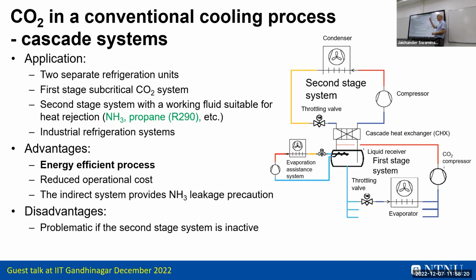No, I would rather send the CO2 in the pipes and suck it back, with evaporators in the different air handling units where you need cooling. You could have one or two centralized CO2 systems connecting all these evaporators, and where you need heat, you put the heat pump to collect heat from all the buildings with a CO2 network, similar to this. That pipe would be much smaller compared to the chilled water pipe, and the pumping power would be zero, because the CO2 comes back as it condenses in the condenser.